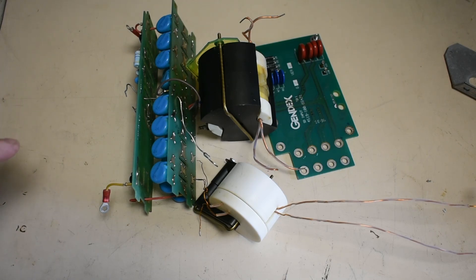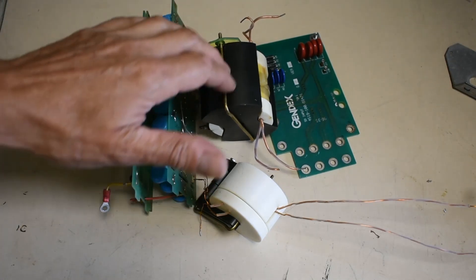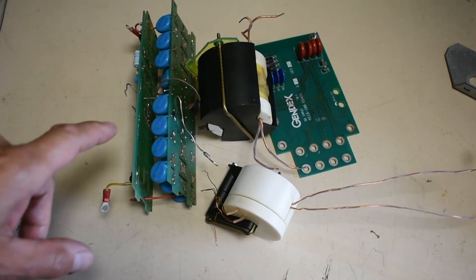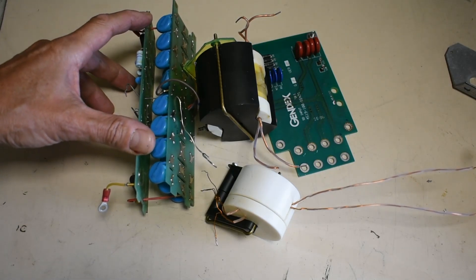This is a high frequency inverter supply so the transformer is actually quite small. So it comprises the high voltage transformer, the power in board, the filament transformer here and voltage multiplier and resistor divider board for sensing output.